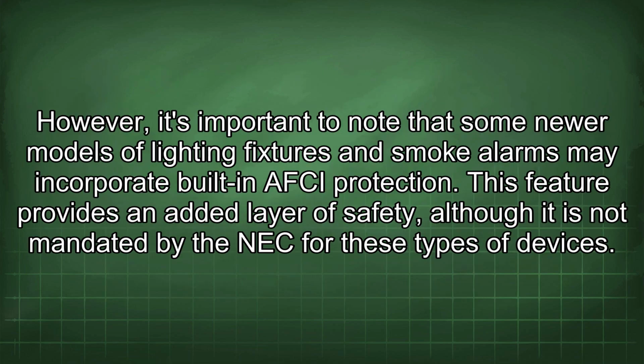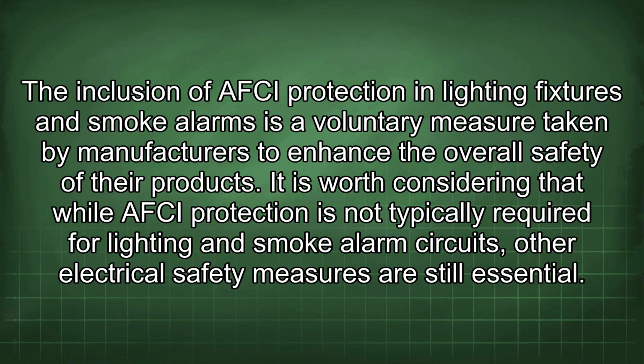However, it's important to note that some newer models of lighting fixtures and smoke alarms may incorporate built-in AFCI protection. This feature provides an added layer of safety, although it is not mandated by the NEC for these types of devices. The inclusion of AFCI protection in lighting fixtures and smoke alarms is a voluntary measure taken by manufacturers to enhance the overall safety of their products.